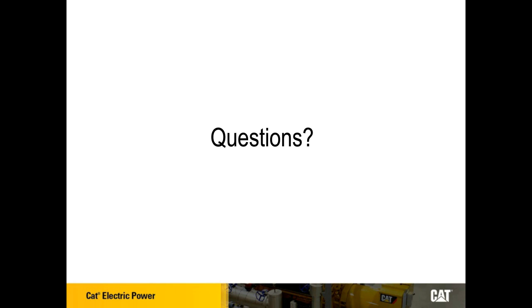It's a good question, Jeff, because propane or LP is a lot easier and less expensive to store on site than natural gas. At the lower end of the size range, as Steve mentioned during the presentation, the small end, it's not that hard to offer an engine that can run on both propane and natural gas, and maybe even automatically switch from one to the other. The challenge we have with larger systems, say nominally 500 kilowatts and up, is that propane has a very different combustion characteristic than natural gas.